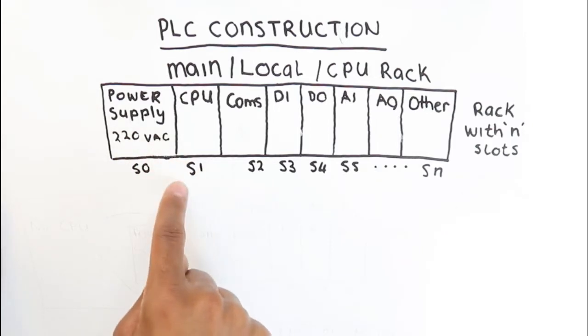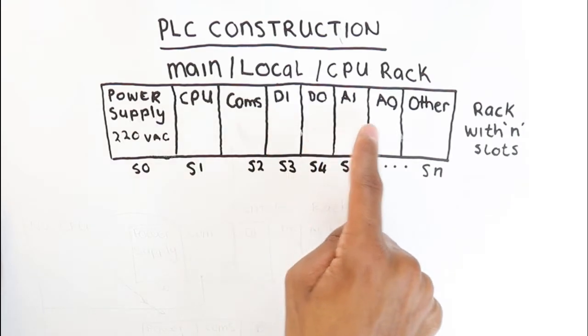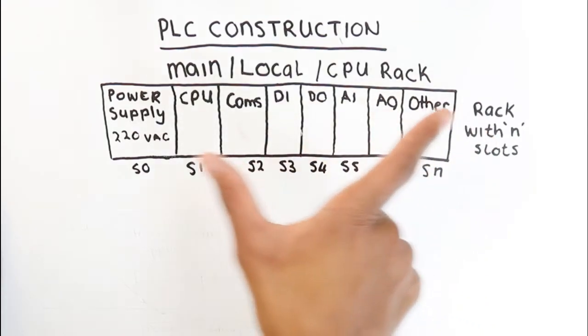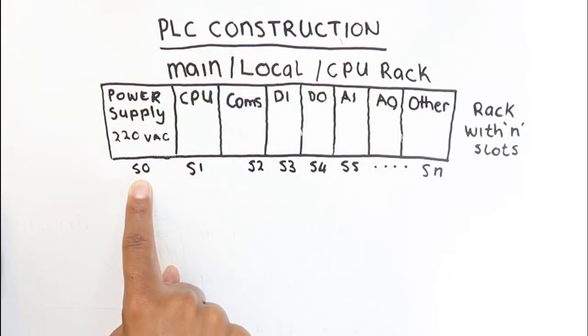The first card that you would have is the power supply, and the power supply usually would require a 220 VAC supply. This is dependent on the rating of the power supply. The function of the power supply is to power up all the other cards that are on that rack. Usually the slot number for the power supply is slot zero because it is the first one on the PLC rack, and it usually does nothing from a control perspective.